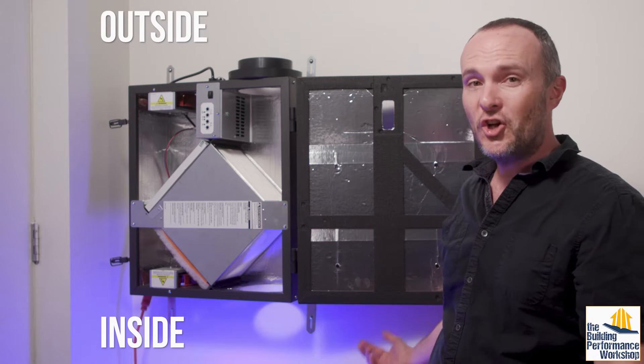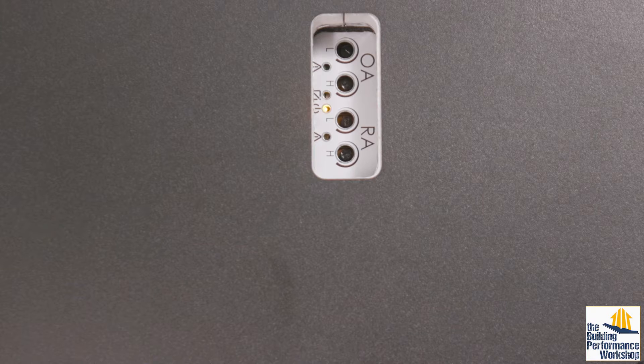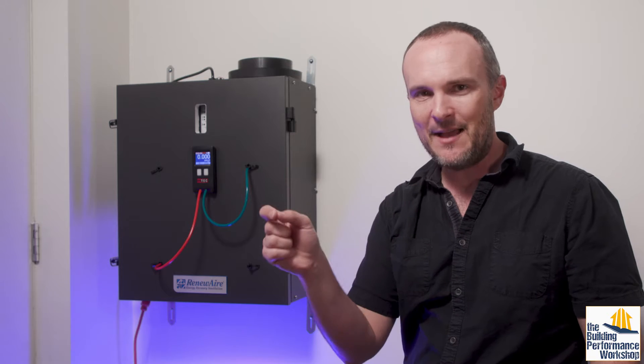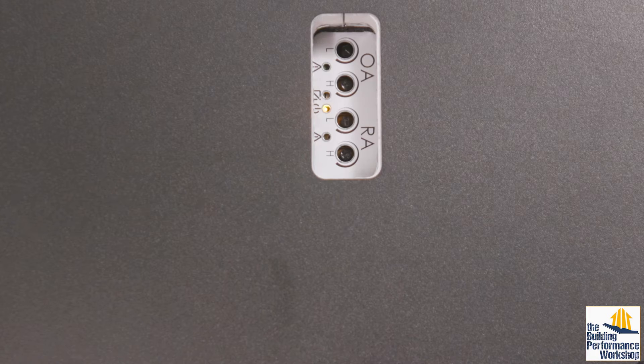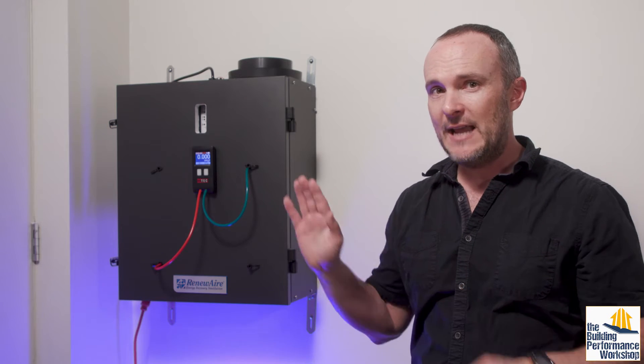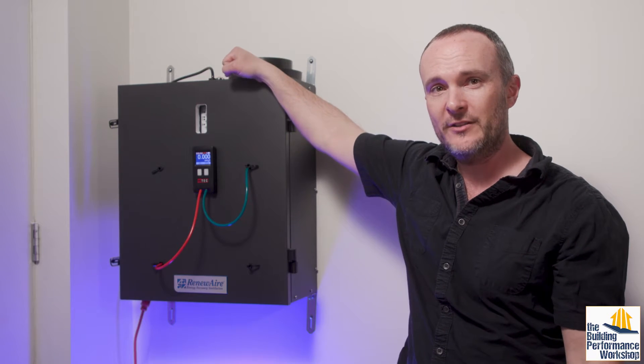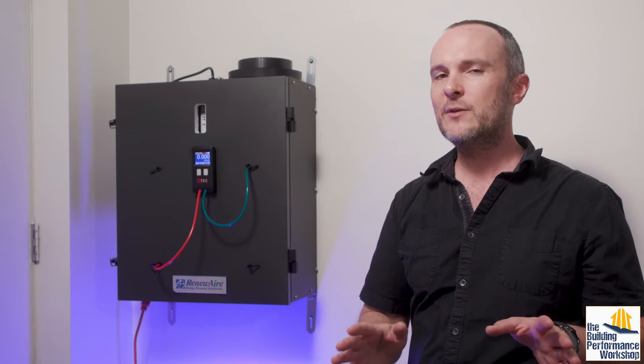Just because this is installed in someone's house does not mean that it's working properly. So you want to use this feature right here on the RenewAire, which is the controls for the EC motors. ECM is what you're looking for, and that means it's variable speed. So I can turn up and down the two fans that run the outgoing air and the incoming air, set them at different levels if I want to, make them perfectly balanced, or whatever I want to do. Some brands have not gone to EC motors — they still use dampers, which means choking off the airflow, which hurts the fan, is a little noisier, and is just not as good. So if you can, try to stick with EC motors.